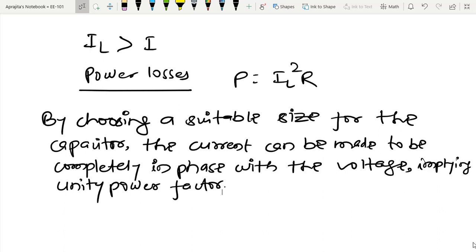So how to minimize the electricity bill? By just putting the power factor correction, meaning adding some kind of parallel or suitable capacitor with the original inductive load. In that way we are doing the same kind of thing.